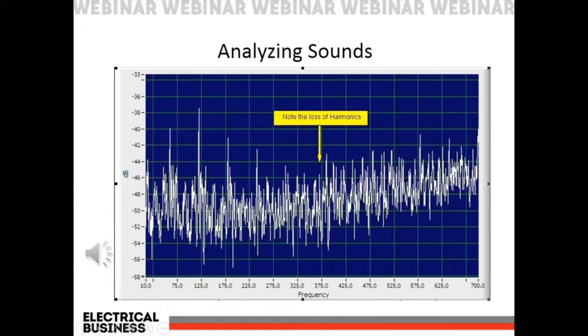I'm not sure if you could pick out those little pops and cracks that were going on inside that sound wave, but you get the idea that those pops and cracks were not evident with the corona. It was more like a buzz, where now we have a buzz plus this popping and crackling. The reason why that's happening will be explained shortly, but basically it's the flashover starting to occur, that low current pathway allowing that to happen. You notice in the spectrum here on the visual picture that we're losing our harmonics. Before, we had a lot of 60 hertz showing up, very rich 60 hertz harmonics.